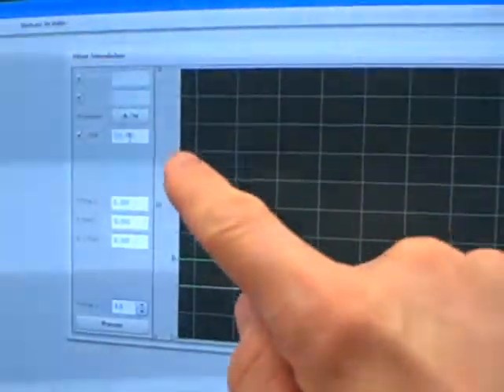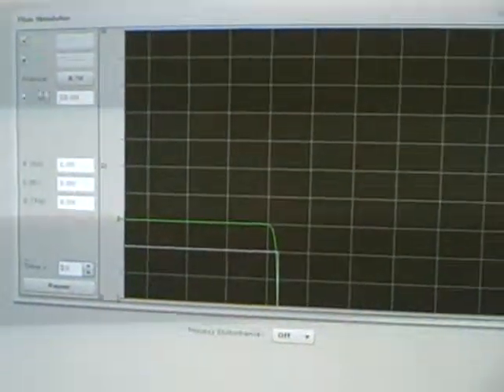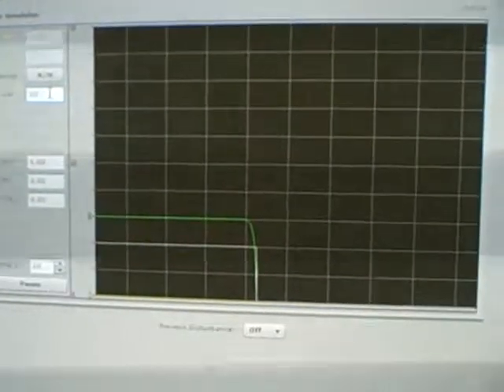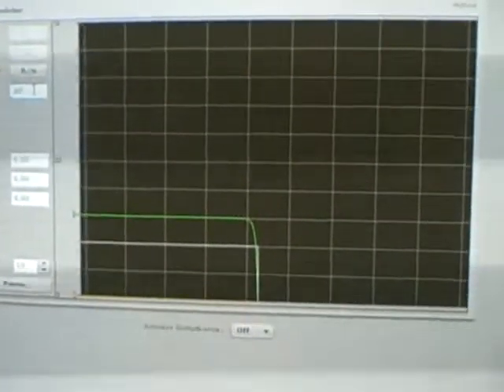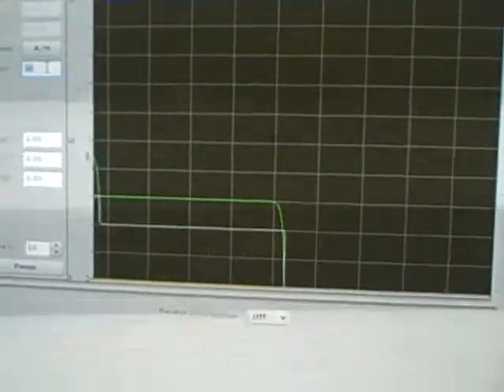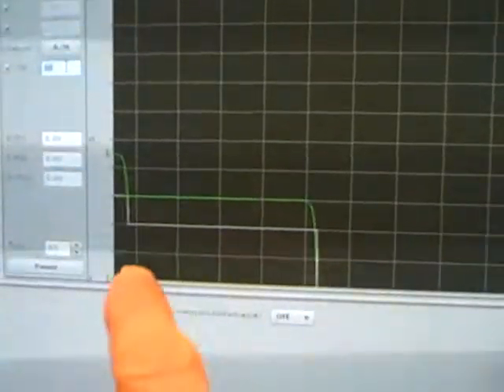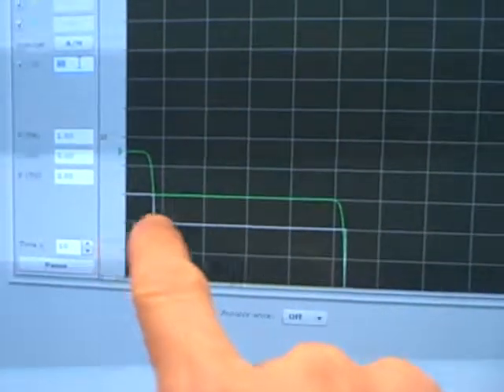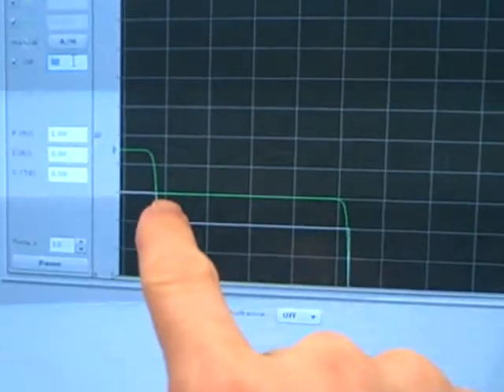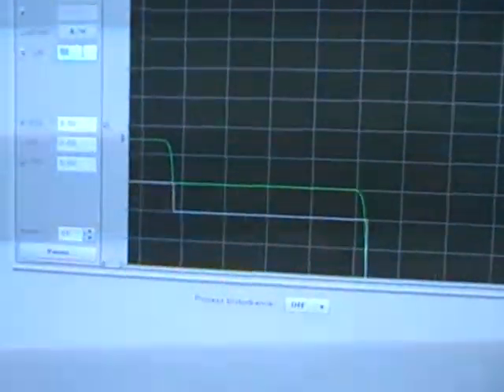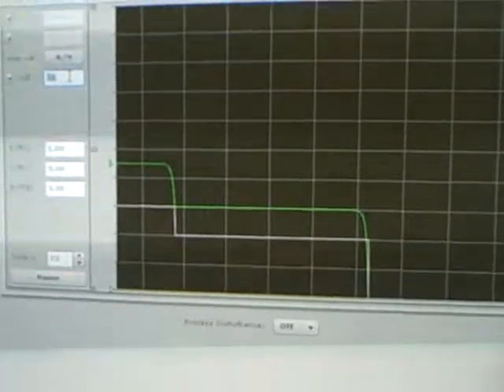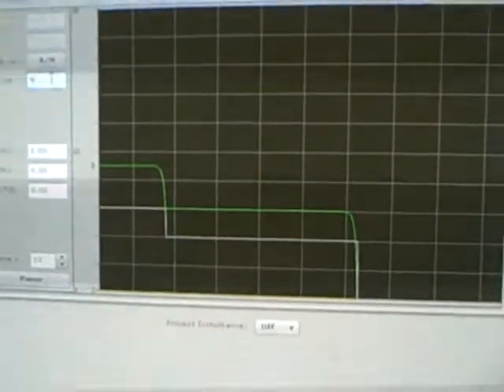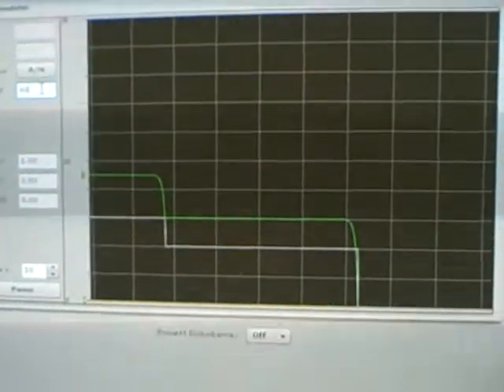We are currently in manual mode, and I'm going to give it a manual mode step change in the output from 20% up to 30%. When we do that, we're going to see the process variable change as well. There goes the white output line stepping up, and there goes the green process variable line stepping up in a first-order lag response. We can see right away this is a self-regulating process.